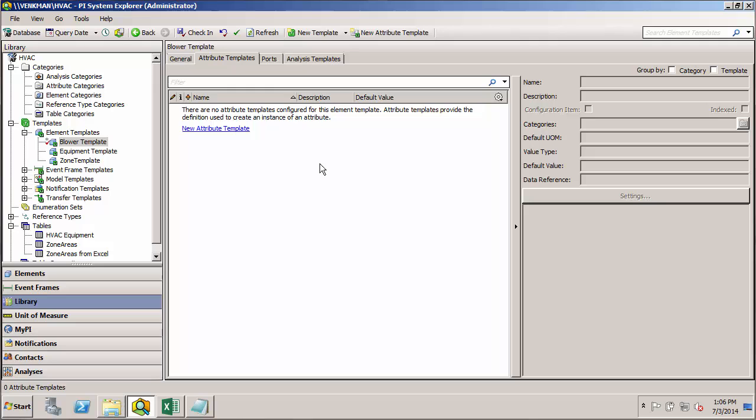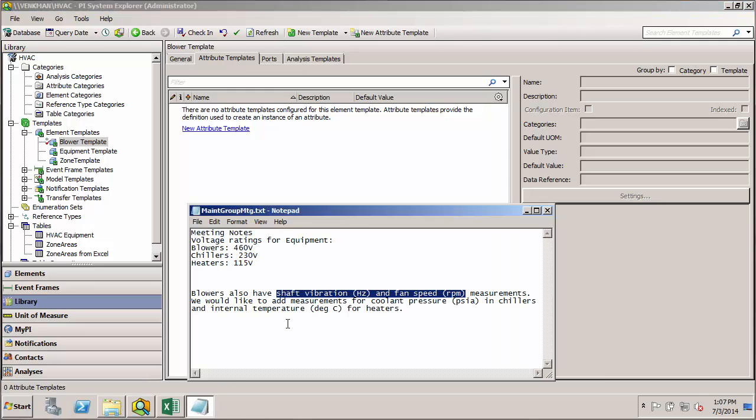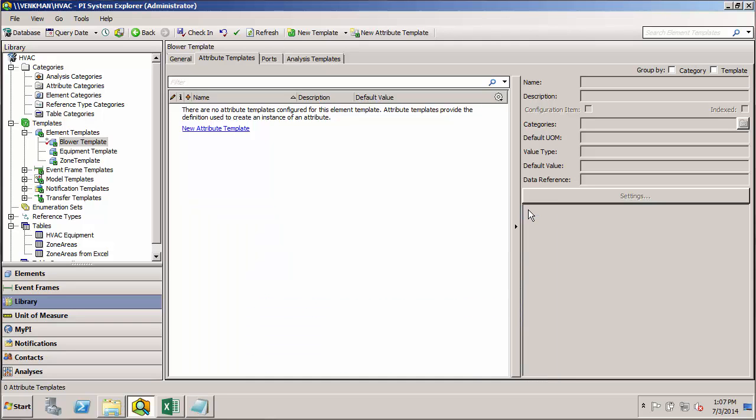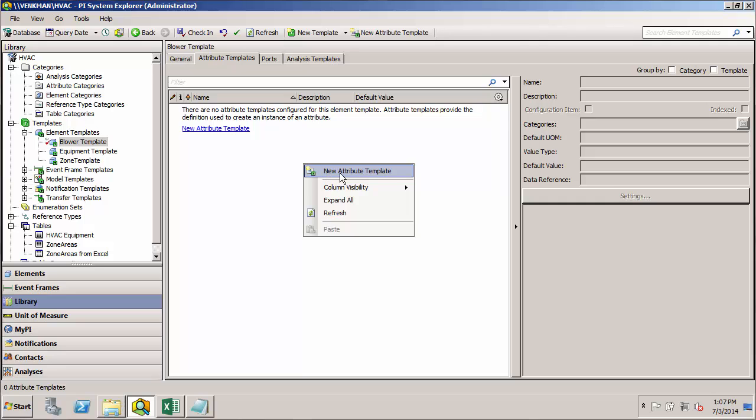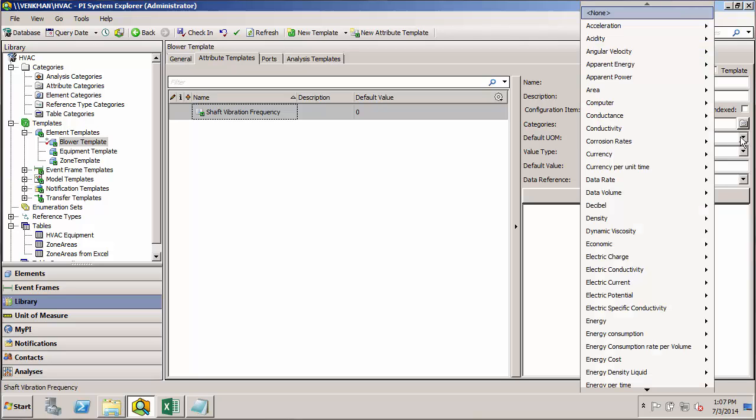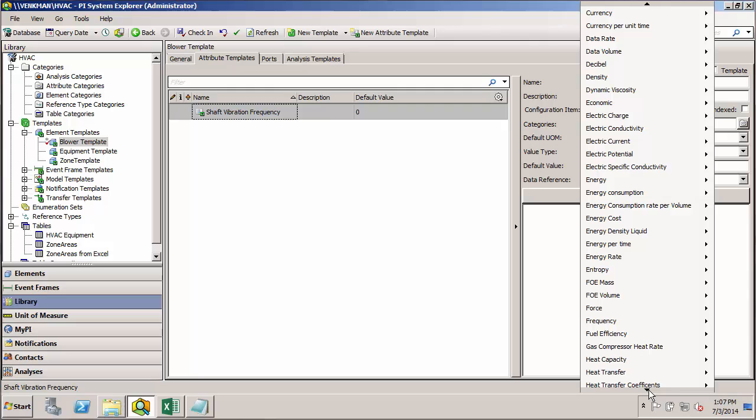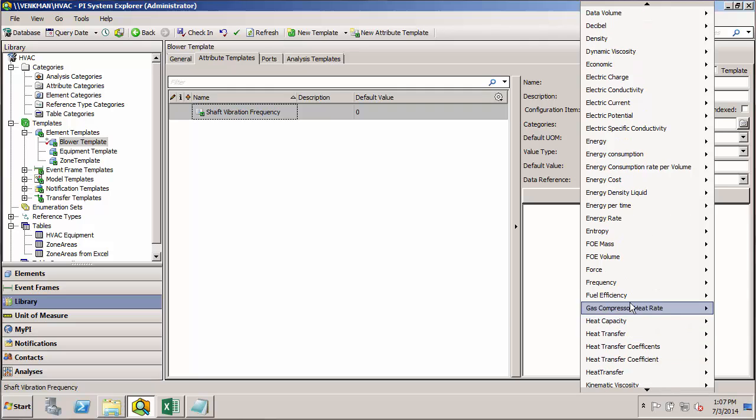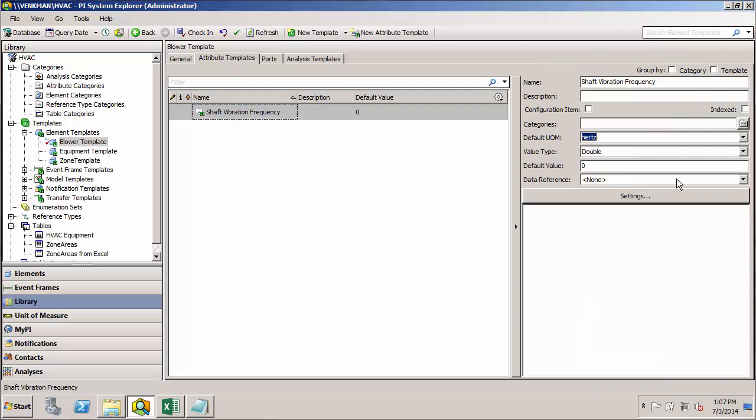Then we want to start adding our unique attributes for the blower. Looking back at our notes, we see that there's a shaft vibration in Hertz and a fan speed in RPM that are being measured and that should be captured in the blower model. So I'll right-click and create a new attribute. Do the shaft vibration frequency first. And we were told that it's in Hertz. So if we find our frequency class in the UOM library, we should find Hertz.